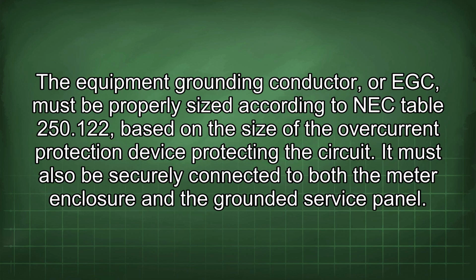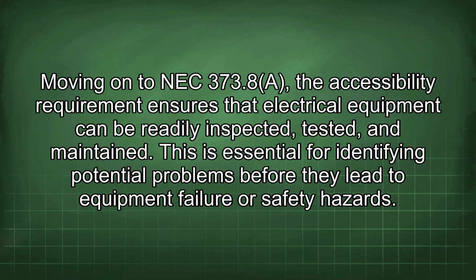The equipment grounding conductor, or EGC, must be properly sized according to NEC Table 250.122, based on the size of the overcurrent protection device protecting the circuit. It must also be securely connected to both the meter enclosure and the grounded service panel. Moving on to NEC 373.8a, the accessibility requirement ensures that electrical equipment can be readily inspected, tested, and maintained. This is essential for identifying potential problems before they lead to equipment failure or safety hazards.